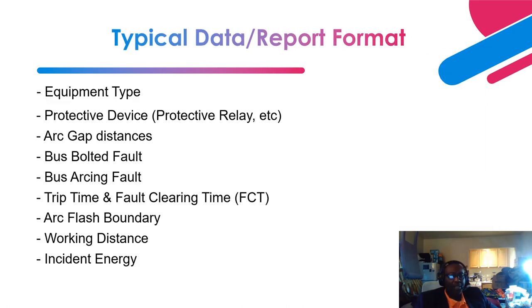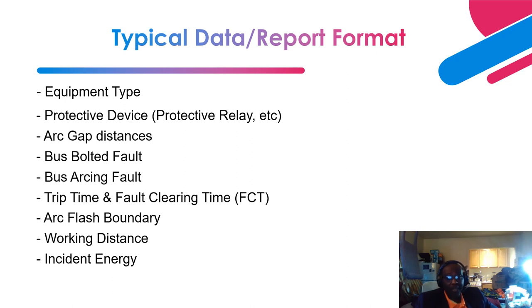Next is a typical Arc Flash report format. The report produced after simulation studies should include at minimum: equipment type, the protective relay utilized, Arc Gap distances, Bus Bolted Fault, Bus Arcing Fault, trip time and fault clearing time, Arc Flash boundary, working distance, incident energy in cal/cm², and I²t — all based on IEEE 1584.